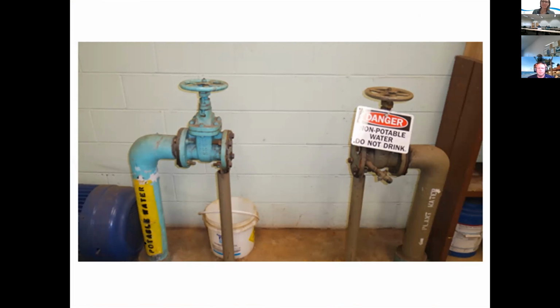So way back when, they had a potable water line. It was a makeup line to the plant water. They decided to use reclaimed water because they have lots of reclaimed water, and so they wanted to use it. So they pulled out the RPBA that was sitting here. Actually, I think this was a double check valve assembly between here. They pulled it out and put on these blank flanges.